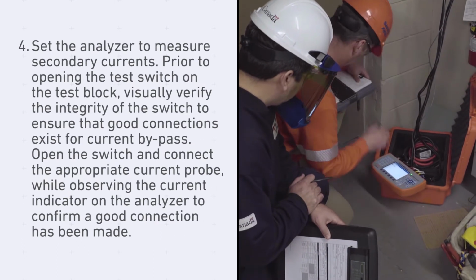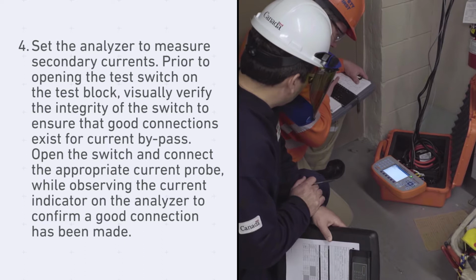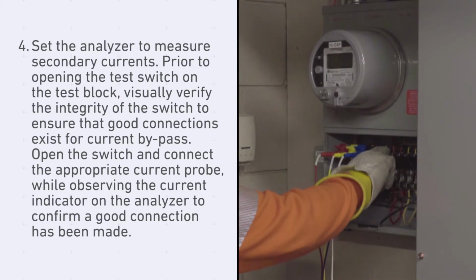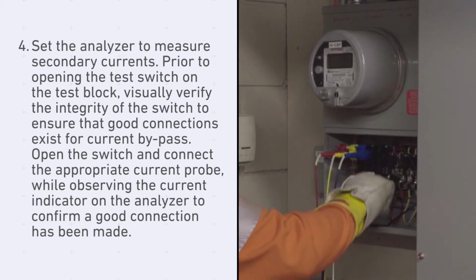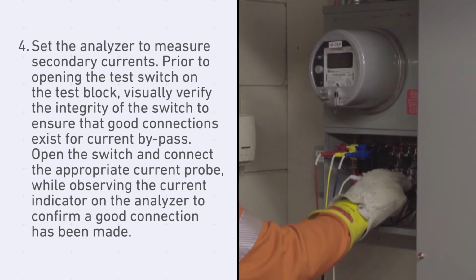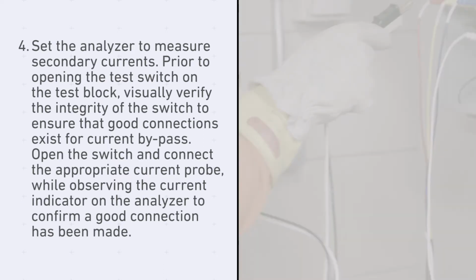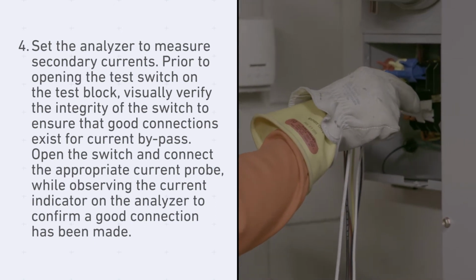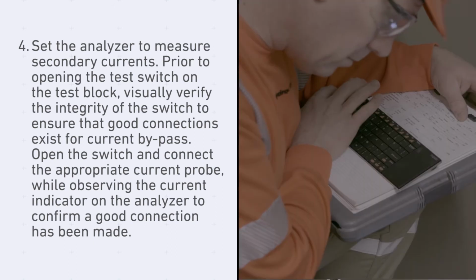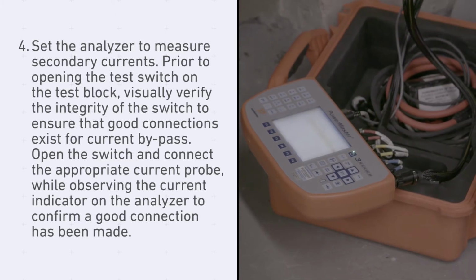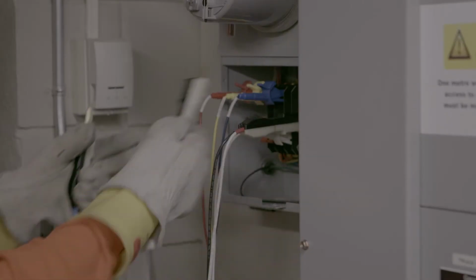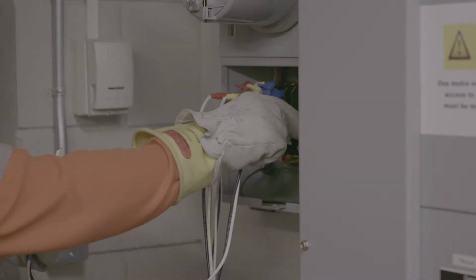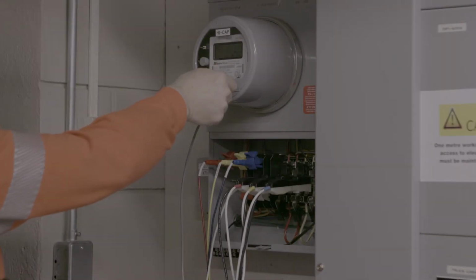4. Set the analyzer to measure secondary currents. Prior to opening the test switch on the test block, visually verify the integrity of the switch to ensure that good connections exist for current bypass. Open the switch and connect the appropriate current probe, while observing the current indicator on the analyzer to confirm a good connection has been made. Be sure to observe the correct polarity of the current probe prior to making the connection. If no current reading is observed, remove the probe and recheck the equipment's setup, usage, and connections.